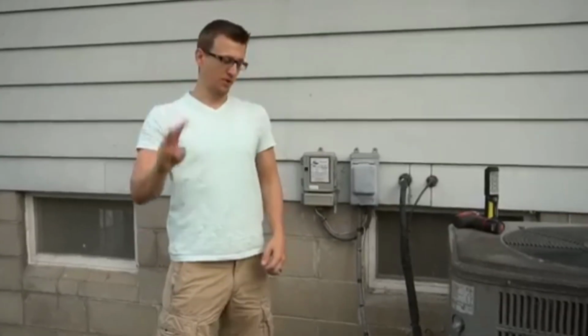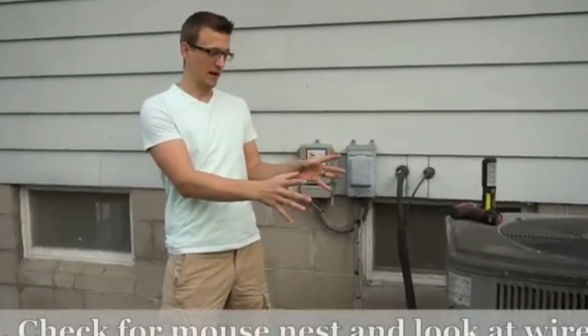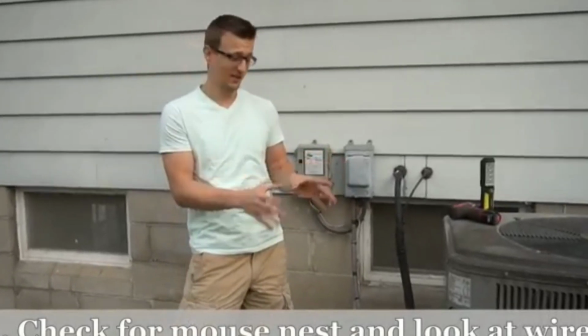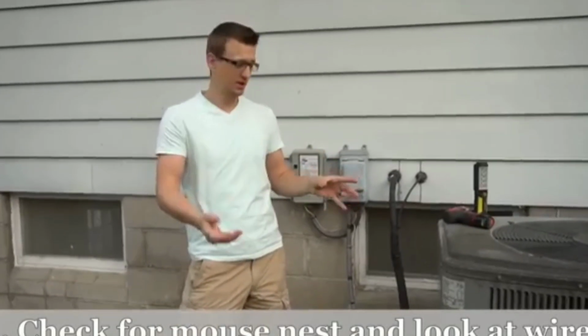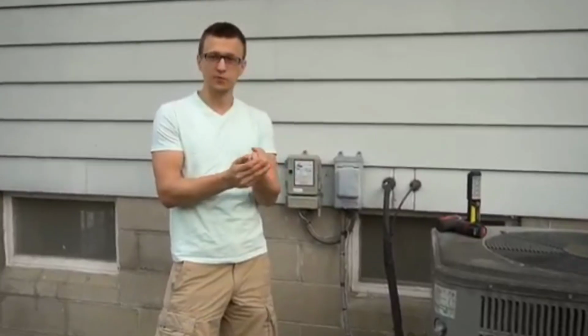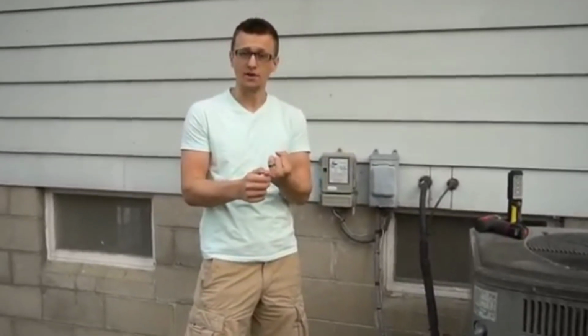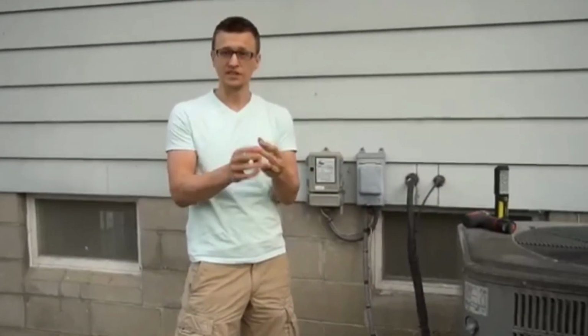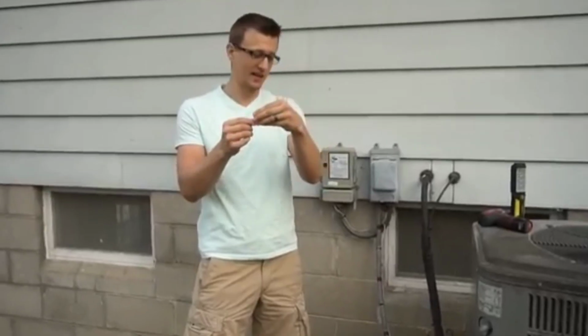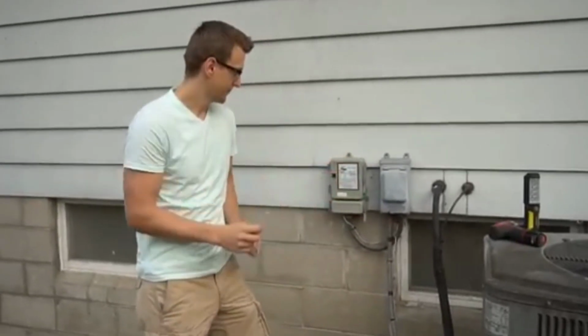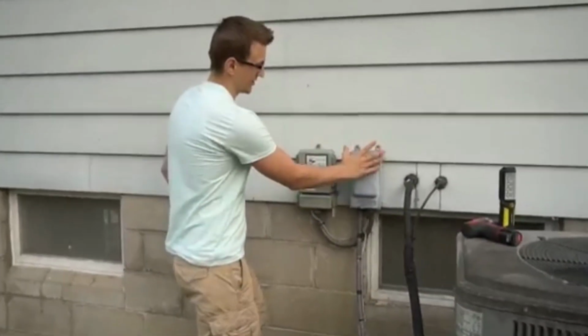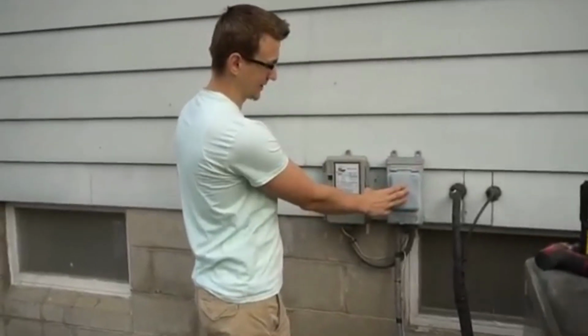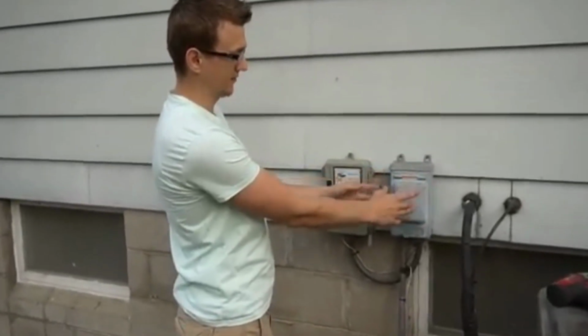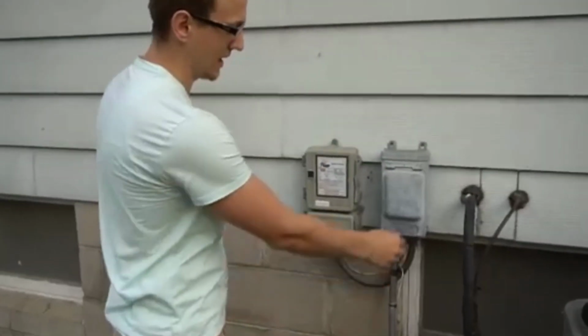And maintenance tip number 3 is to check if you actually have a mouse nest that was built during the winter, and to check your wires for any broken wires, bare wires, or any broken connectors on those wires, the wire connectors. So to do that, first you have to locate your disconnect. This is your electrical disconnect. Usually it'll look like that, either a metal box or a plastic box.